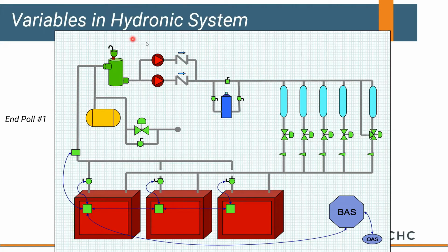Let's talk about some of the variables we have in our hydronic system. We've got some system pumps that are on drives, and they're going to speed up or slow down as we have changes out here in the system. So these might be offices or classrooms that we have water flow going through. They're controlled with two-way valves.